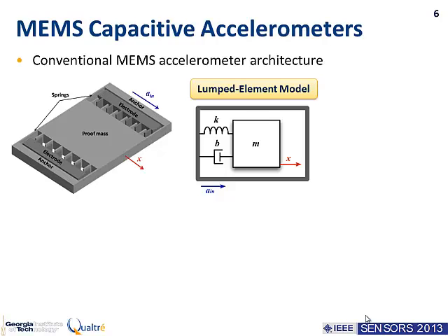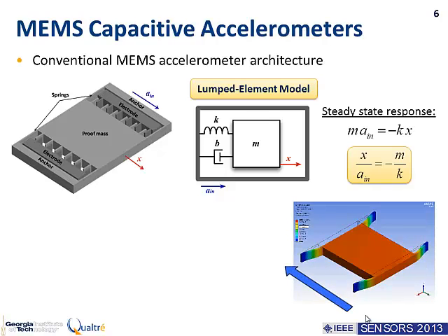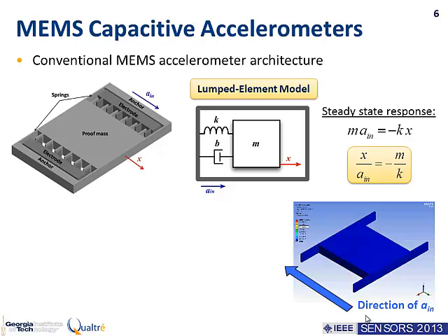So if we take a look at the static response of this device, we see that if we apply an acceleration, we're going to get a force given by Newton's second law of motion, which is basically the mass of the structure times that input acceleration. And as I said, in a static case, that force is going to be counteracted by the spring force given by Hooke's law, which is K times X. So our scale factor for the static case is just going to be the mass of the structure divided by the stiffness. So basically, the amount of displacement that we get per unit of acceleration depends on how big of a mass we have and how small of a spring constant we have.